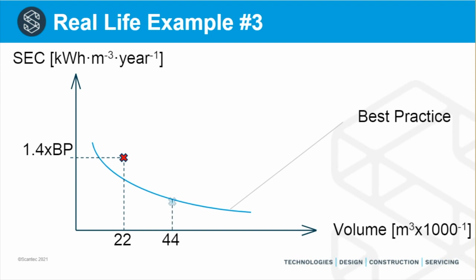So what we see here is two refrigeration systems that are conceptually identical. Both systems have 4 reciprocating compressors in two-stage mode, 2 low and 2 high. This plant that you see here, where the number 22 is, this is a 22,000 cubic meter warehouse that was installed approximately 10 years ago for a transport company here in Brisbane. That plant used 1.4 times best practice. The SEC value was 1.4 times best practice.